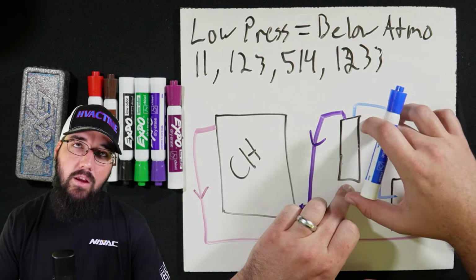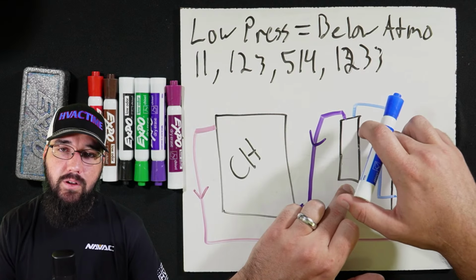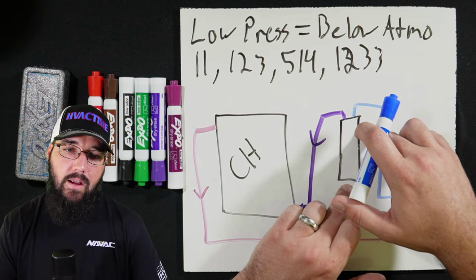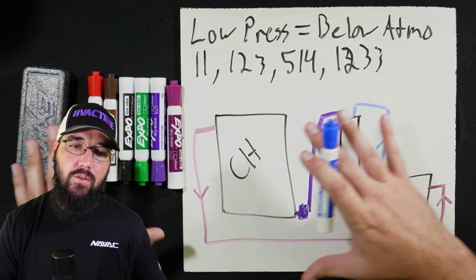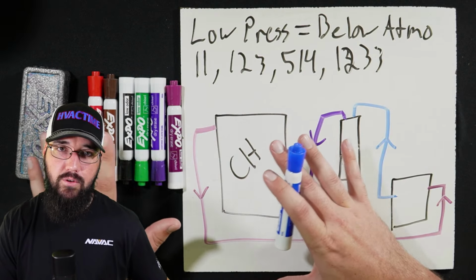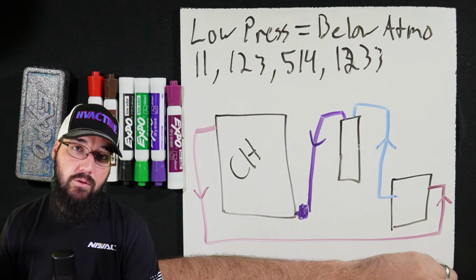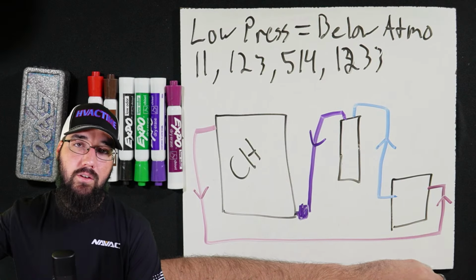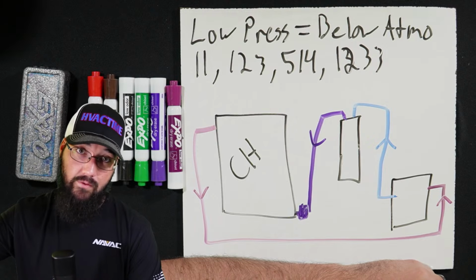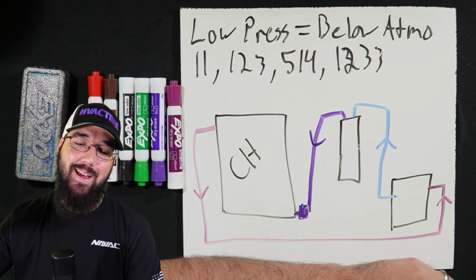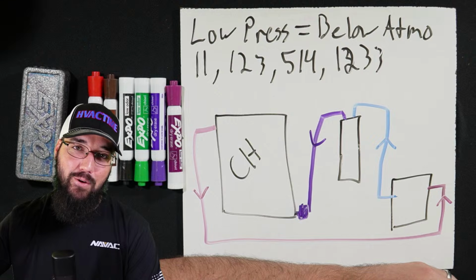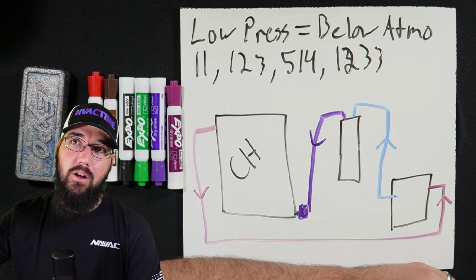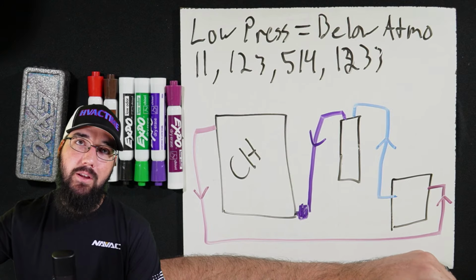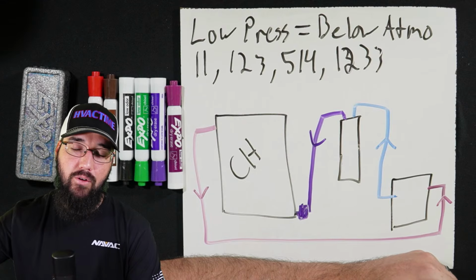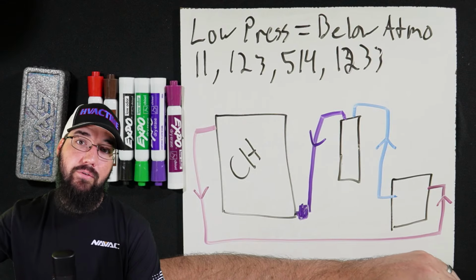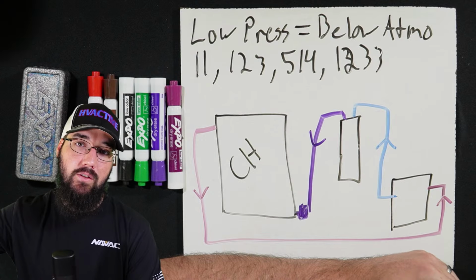Or you can set it up so that if your refrigerant is in a recovery cylinder, instead of using a machine to push that refrigerant over, you could just hook up, hoist that tank in the air. You have to flip that tank over, so keep that in mind. If I said liquid line, I made a mistake. I meant to say vapor port.